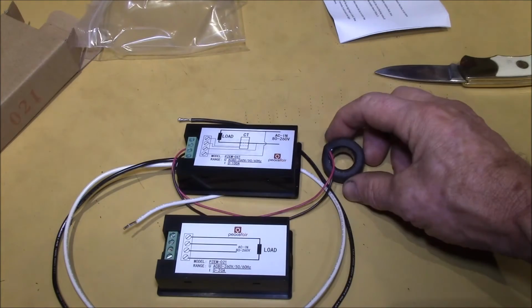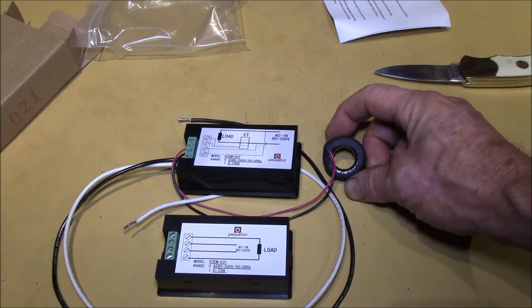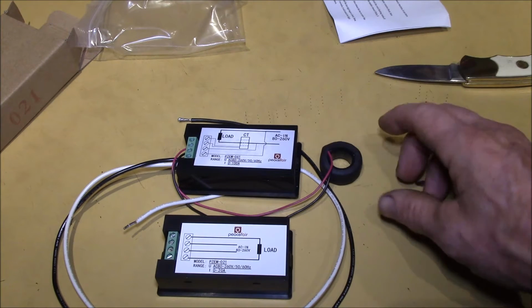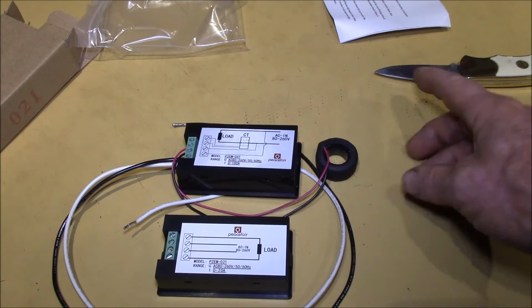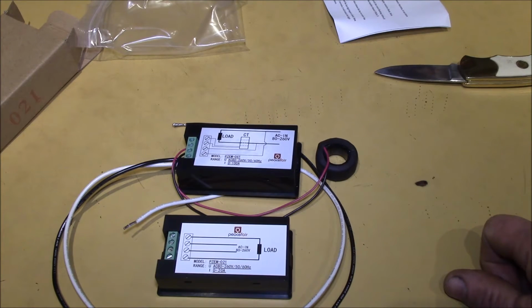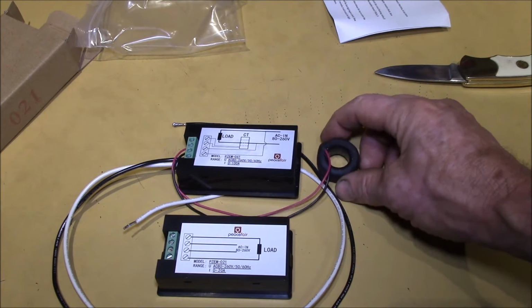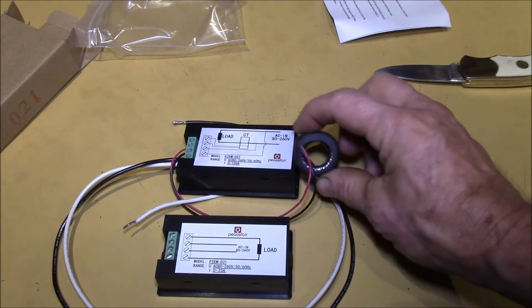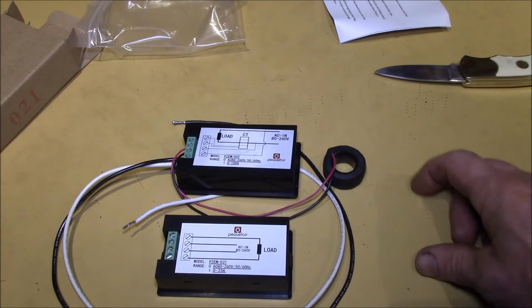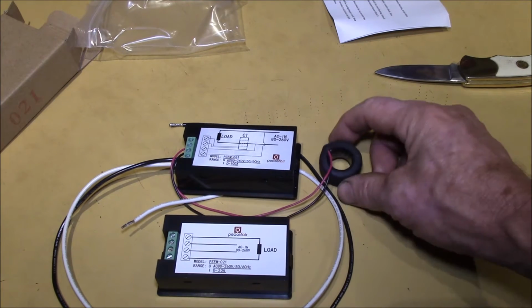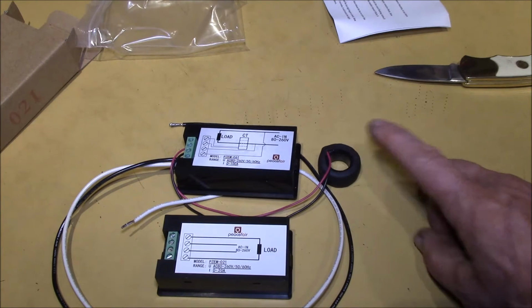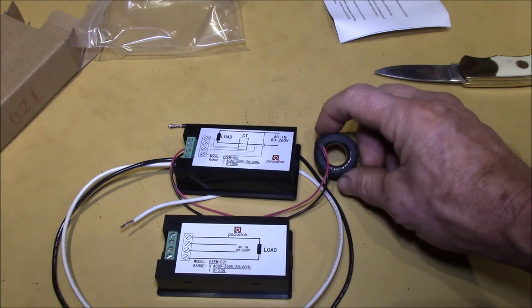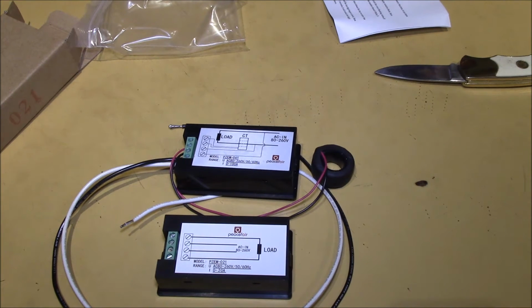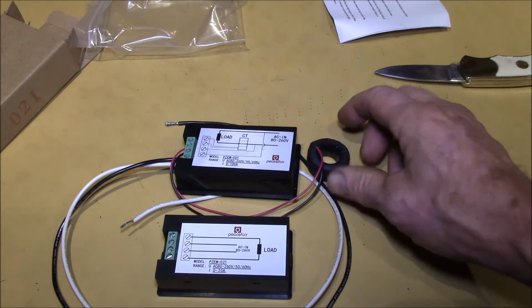I have two of these meters. I think this one reads about 400 milliwatts at no load. The other one reads about 600 milliwatts, and they both read about 40 milliamps at no load, with no current flowing through here. And I've tried moving this current transformer to various parts of the power supply, and it just seems to be something inherent with the calibration of these. Now, if I were running a 100 amp load through here, 40 milliamps doesn't mean anything, but when you're trying to measure like a 1 watt LED bulb, having to remember to subtract 600 milliwatts from whatever reading you get just gets a little bit tedious.